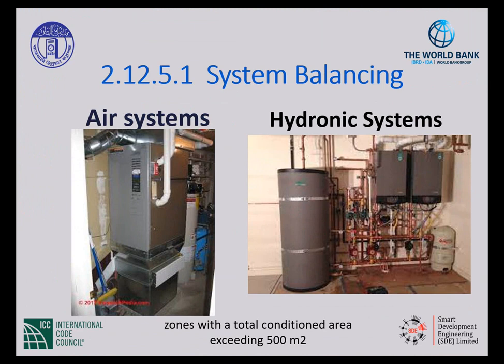System balancing. Construction documents require that all HVAC systems be balanced in accordance with generally accepted engineered standards. It requires that a written balance report be provided to the owner or the designated rep of the owner, and this applies to zones with the total conditioned area exceeding 500 square meters. So 500 square meters or larger conditioned areas, conditioned meaning am I heating or cooling it, those need to have a balancing.